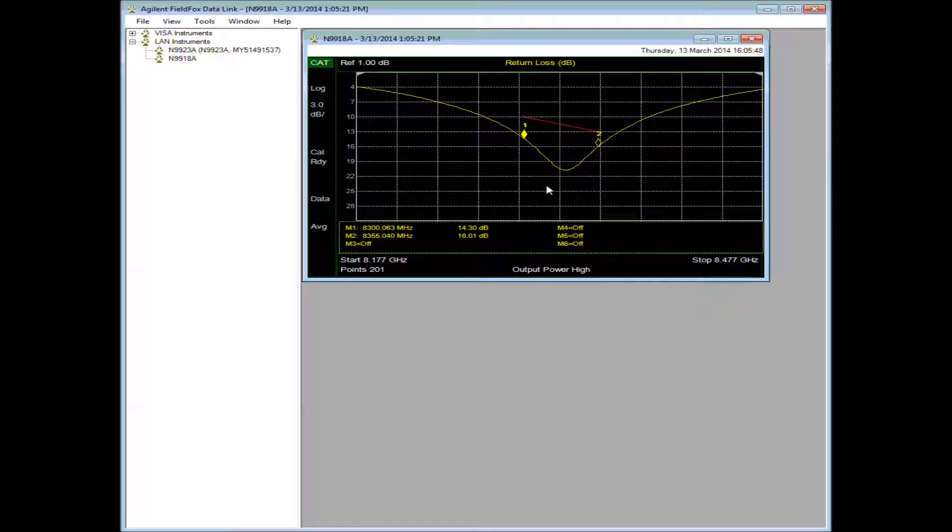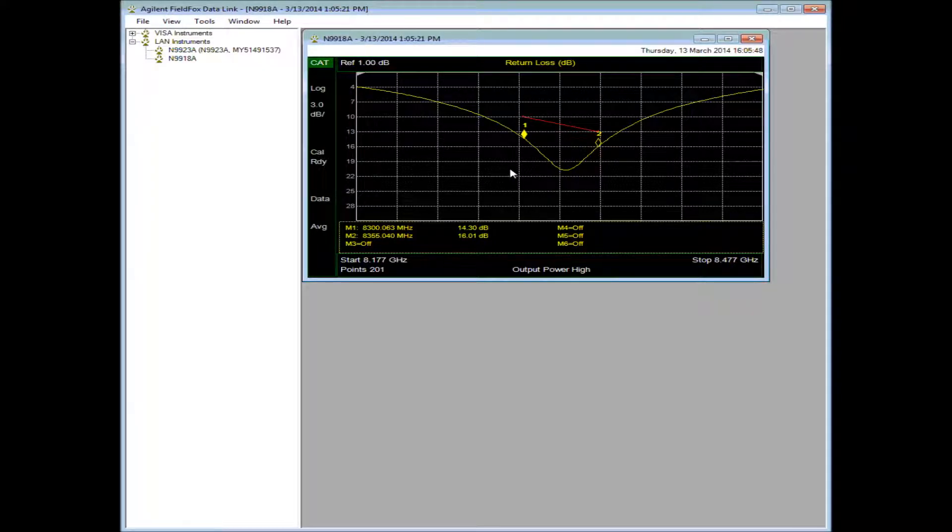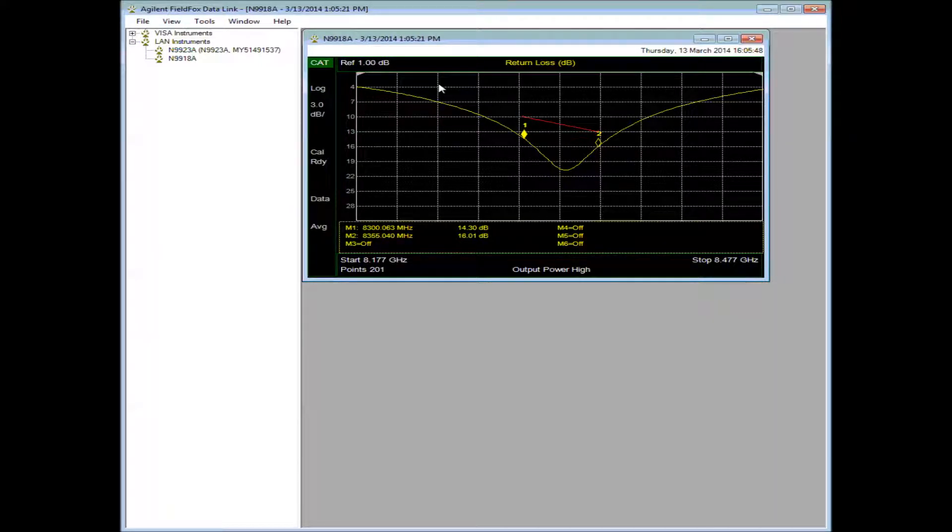Once I exit, you'll see that the limit line slope changed. So this is post-processing. If I look at the instrument right now, the limit line is still a flat line at 10 dB. We can also do things like add markers.